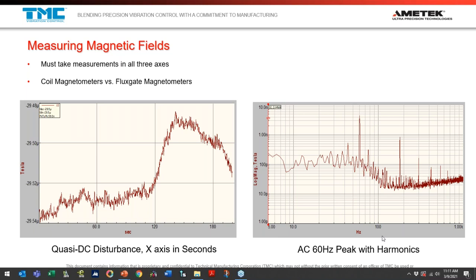For AC fields, we don't really care about the time domain. What we care about are the component frequencies, so we look at an FFT — a fast Fourier transform — of the signal to identify frequencies of the alternating fields. Here's a very common signature of a 60 Hz field: on the x-axis from 10 Hz to 100 Hz, we see a peak of roughly 45 nanotesla at 60 Hz. What's really interesting is that we also see the harmonics — a 120 Hz harmonic, a 300 Hz harmonic — and they trail off as we get into higher frequencies.